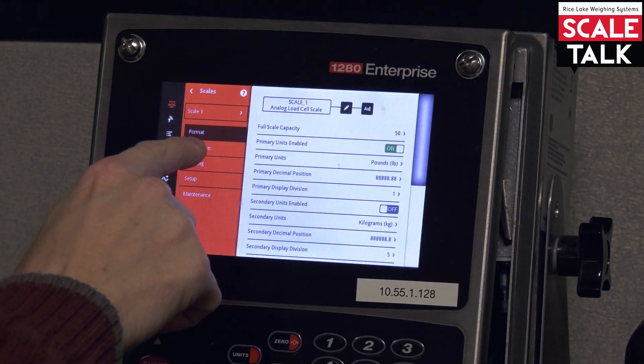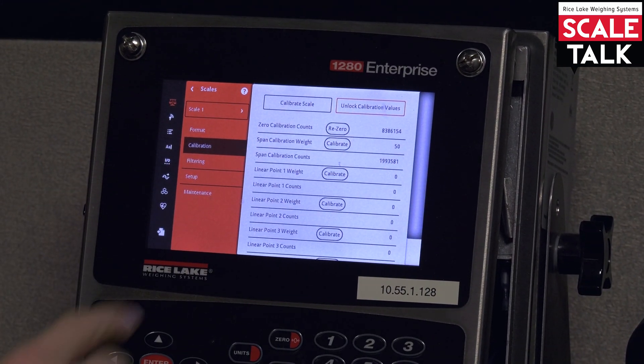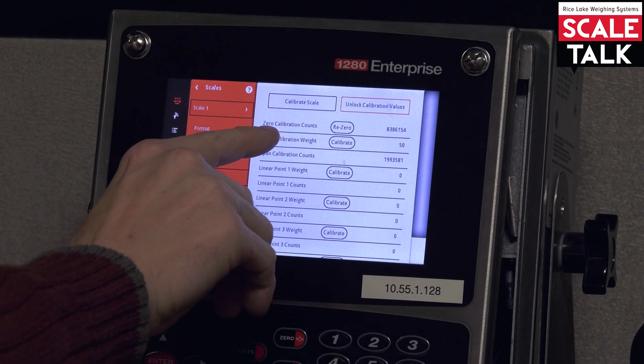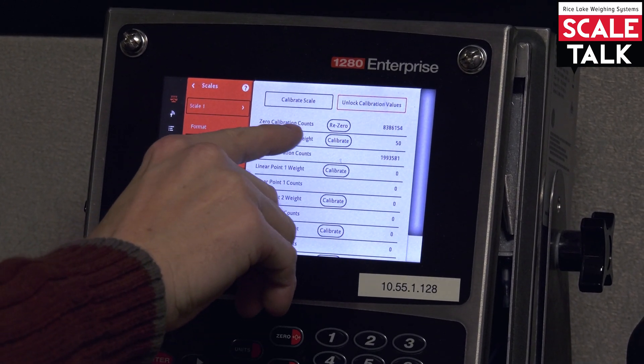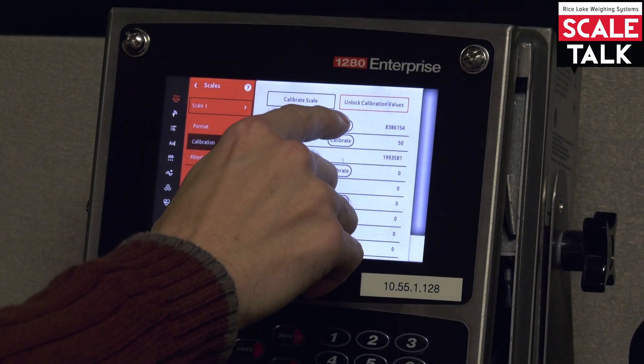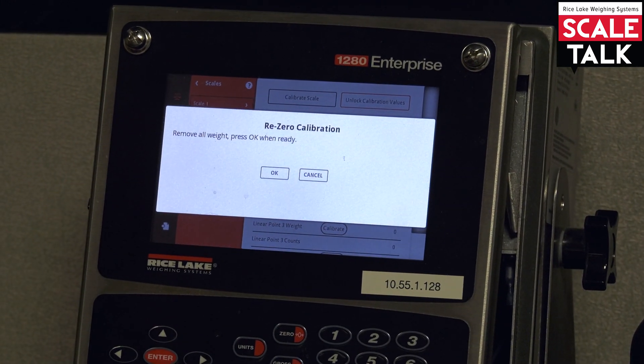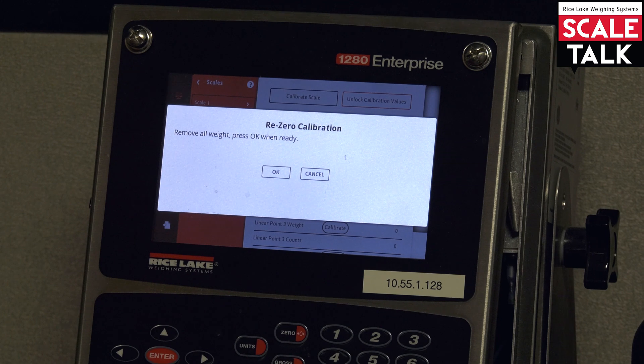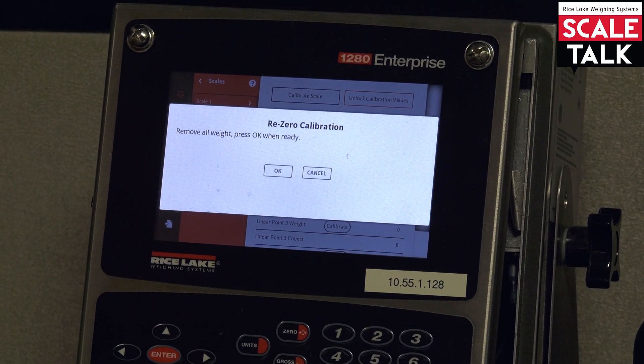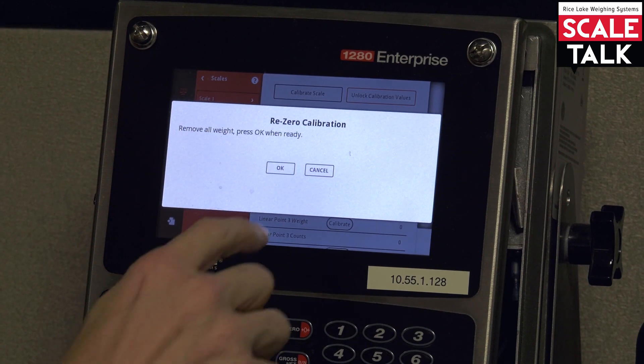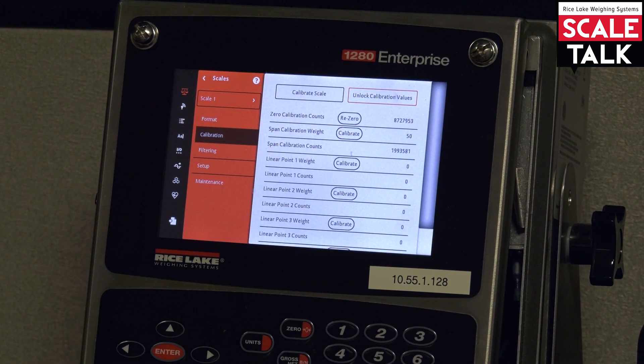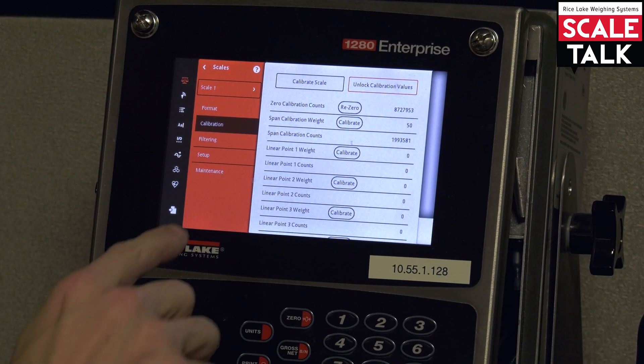So let's hop back into our menu. Go to scales. Go to calibration. And right here you see we have this little option here called re-zero next to zero calibration count. So we're going to go ahead and press that re-zero. It lets us know to remove all the weight. So we don't have any weight on our scale at the moment. This is what's reflecting our zero. And then we'll press okay. Now we'll save and exit one more time.